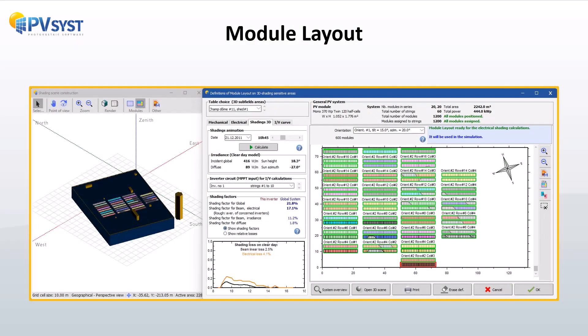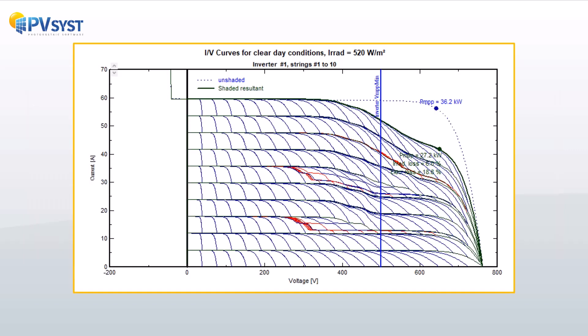The module layout tool is used to calculate the electrical mismatch loss caused by shading in the PV system. It involves assigning positions to each PV module in a 3D scene and connecting them as strings according to the defined subarrays in the system window.